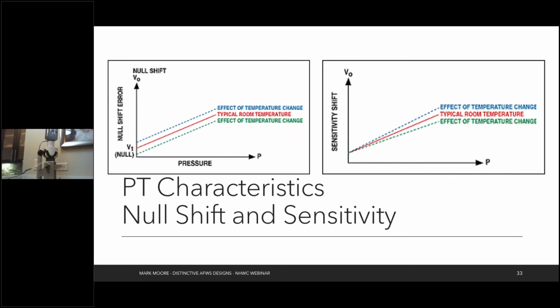So here are some things you might see. What would cause a PT to be out of calibration? Well, one thing that temperature can do is it can have what's called a null shift error. And so the relationship between the voltage and the pressure can shift. Basically, it's offset. So the slope is the same, but the actual up and down position of it, that offset, is dependent on temperature. On the other hand, you can have a sensitivity shift, which is the opposite. The offset is the same on all these tests, but maybe when it's colder or warmer, the slope changes. And so you won't have the same results at different temperatures when you really are expecting it to.